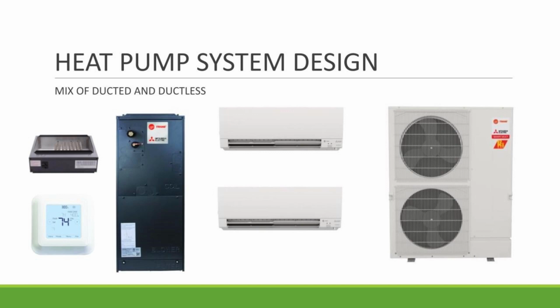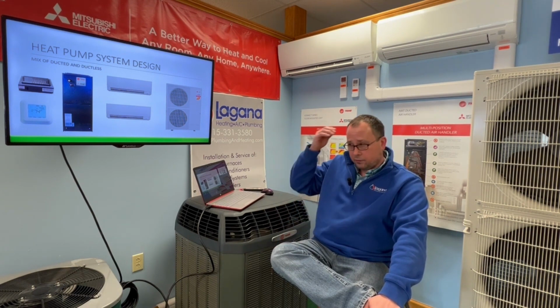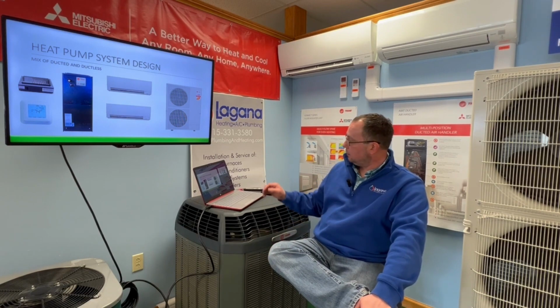Some other options would be a mix of ducted and ductless. In this case, we can utilize an air handler with possibly an existing duct system. We can also incorporate that into a multi-zone style system where we may have an air handler and also maybe some individual head units. An application like this is really good when you have an older home, maybe it doesn't have ductwork to the second floor. We can also add backup electric heat strips in a system like this.